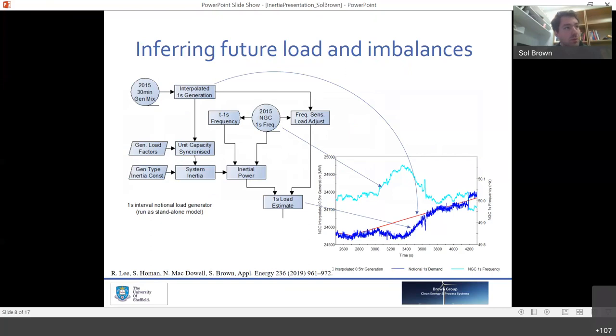Our problem is if we want to project further into the future and understand how new mixes of generation and demand will be affected, and how we might want to deploy either inertia or frequency response to that, we need to understand what the frequency will look like on a given day-to-day basis. And so we've come up with a way of back calculating a load imbalance, and then from that feeding forward a frequency profile. If you want details on this, I can provide you with a publication. But it's basically a way of pulling forward a frequency profile that we would then look at how a system would react to.